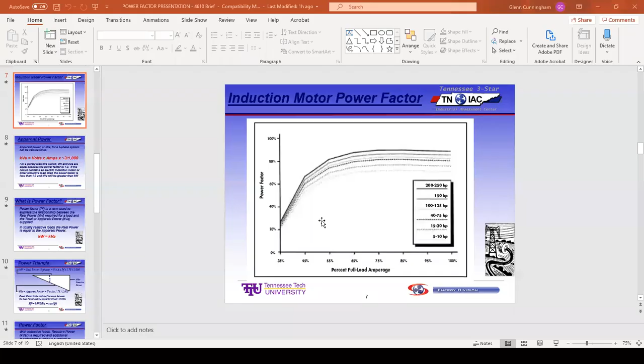Well, the larger presentation goes into this. What happens in a capacitor is that it basically stores electrons and then discharges them back into the circuit. So that action basically will retard the voltage waveform relative to the current. With the low power factor, you've got the voltage peaking first and then the current. But if you add the right amount of capacitors, you can slow that voltage waveform down and put it more back in phase with the current. And so that's why you want to do that.